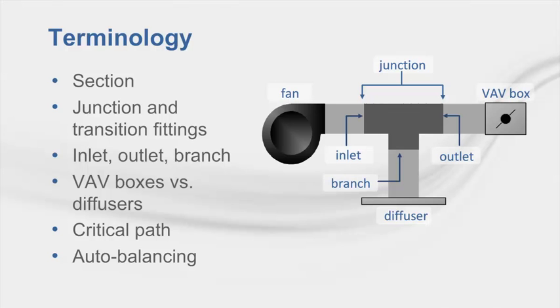VariTrane Duct Designer's database contains hundreds of ASHRAE and United McGill fittings. Junctions have inlet, outlet, and branches. The inlet is where the airflow enters the junction. The outlet is the straight-through path of a junction, and a branch is any other leaving path from the junction. VAV boxes terminate a duct run. Diffusers are the final link in a constant volume duct system, connecting the duct system directly to the space.